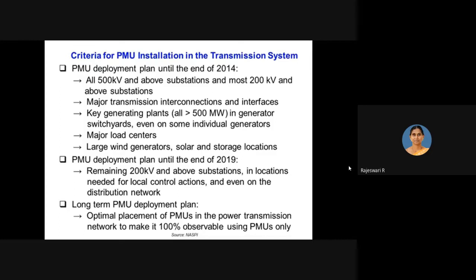So in that tie line connecting two major areas, which needs to be monitored perfectly, such interconnecting transmission lines are selected to place this PMU. Also, key generating plants delivering greater than 500 megawatt are selected, and also large wind generators, solar and storage locations. These are all the locations where PMUs are being placed, as of 2014.